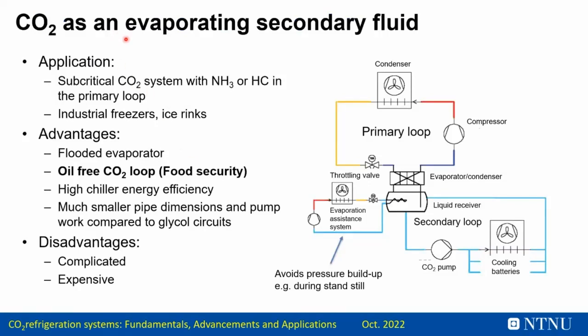So when CO2 is used as the evaporative secondary fluid, we replace a typical glycol with CO2. This has a significant impact on the power consumption, on the efficiency, because we have very efficient pumping with CO2 and we have flooded evaporators. We have an oil-free CO2 loop. In this loop we can pick up all the heat at the different places and it is very safe because there is no critical fluid near food, for example. That's very, very good. Instead of having a poisonous fluid around, where the leakage might destroy all the harvest, with CO2 this is very safe. And we have a very high chiller energy efficiency, and we have a very small pump and pumping power compared to glycols. It's a bit expensive, but it is a very solid installation.